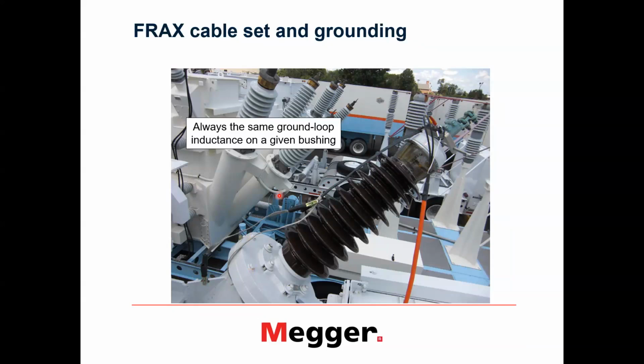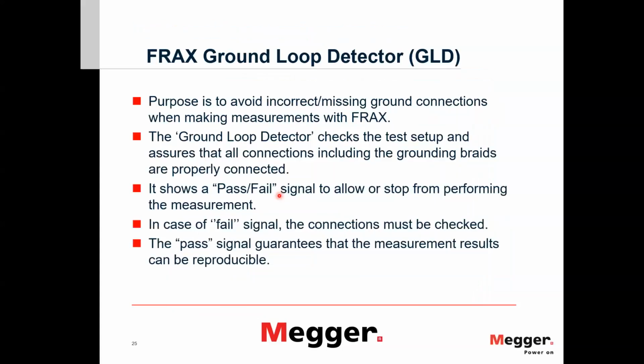So this is important. And in order to help with such things as good groundings and no disconnections, in FRAX we have provided an automatic ground loop detector, which by pressing a button checks all ground connections, and if everything is fine, you have a green light and you can go on and measure. One thing I can mention is that it is not mandatory to use the ground loop detector. It does not make a measurement better in any way. It is more for making sure that you have done a proper setup. And this is one of the conditions of good and successful measurement and subsequent analysis.